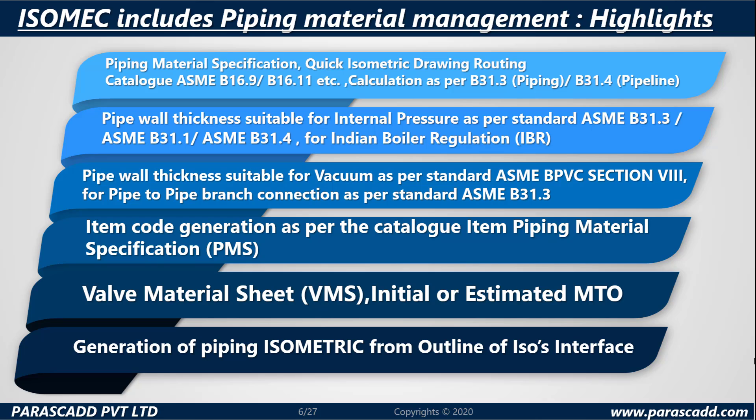Pipe wall thickness must be suitable for internal pressure as per standards ASME B31.3, ASME B31.1, and ASME B31.4, as well as for Indian Boiler Regulation (IBR). Pipe wall thickness must also be suitable for vacuum as per standard ASME BPVC Section 8, and for pipe-to-pipe branch connection as per ASME B31.3. Item code generation is available as per the catalogue item piping material specification (PMS).